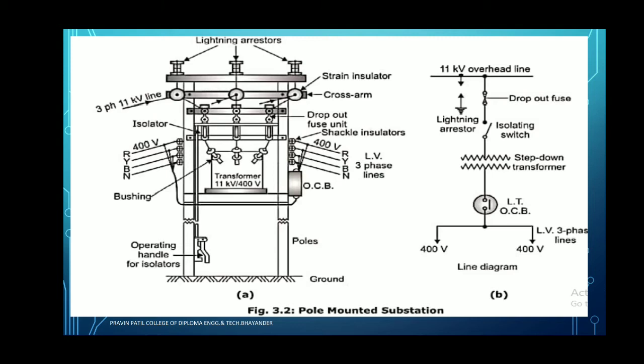Near that 11 kV line, the lightning arrestor is connected. The function of the lightning arrestor is to divert high voltage towards the earth and provide protection to the substation. One terminal of the lightning arrestor is connected to the 11 kV overhead line and the other terminal is connected to the earth. The main function of the lightning arrestor is to divert high voltage, or a direct lightning stroke, towards the earth.